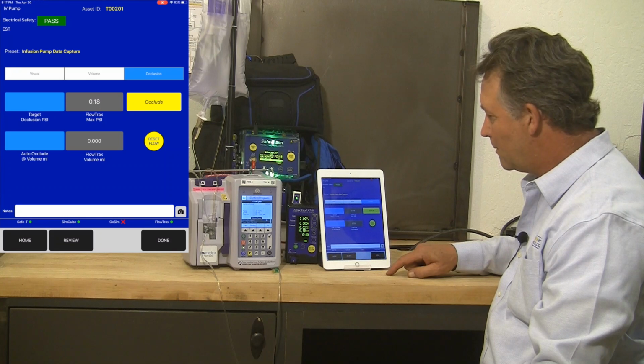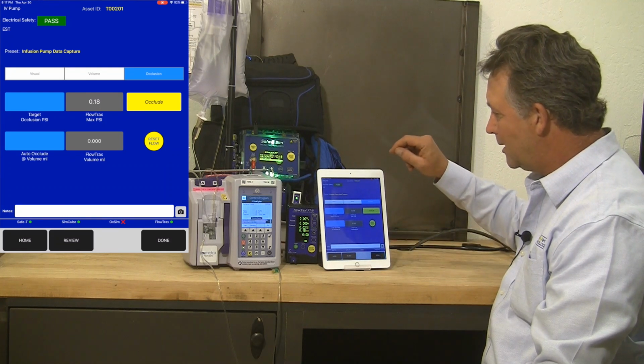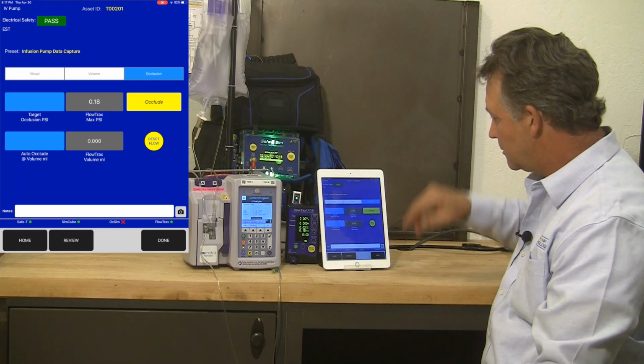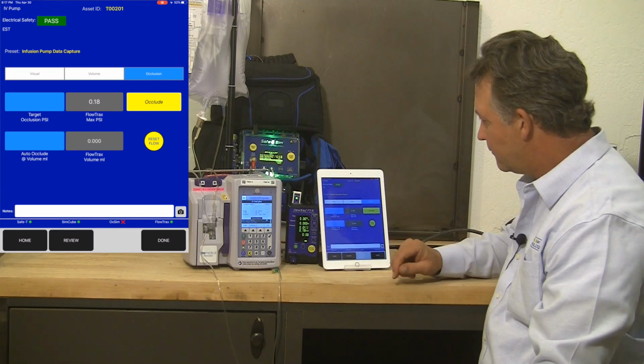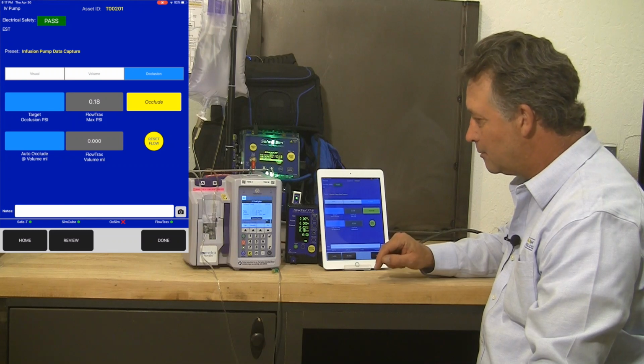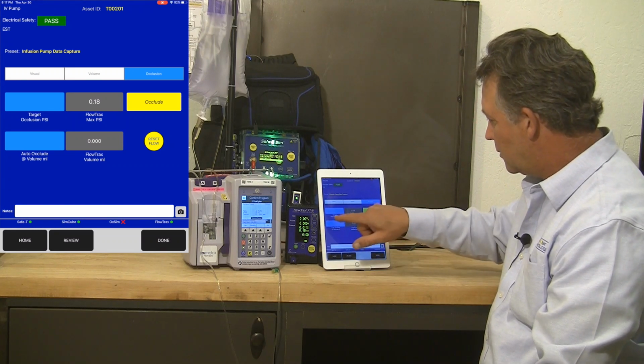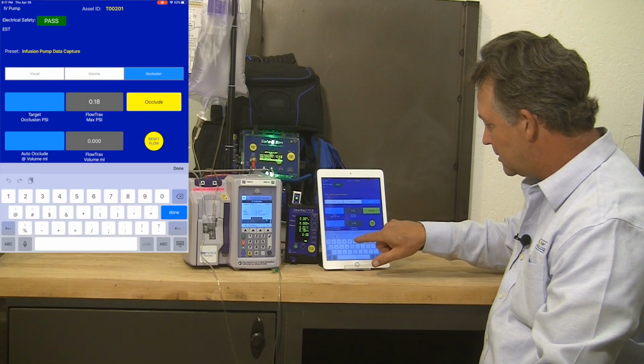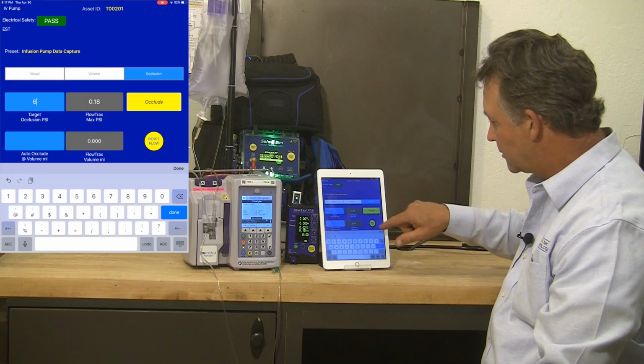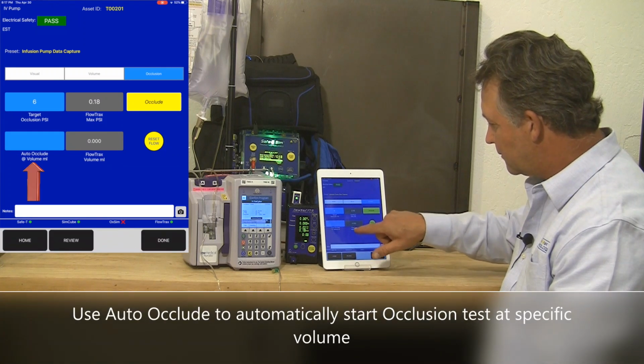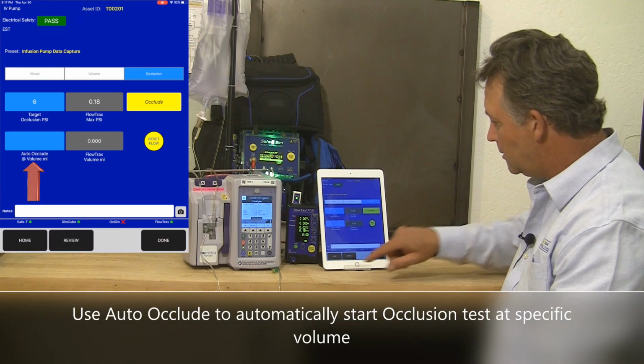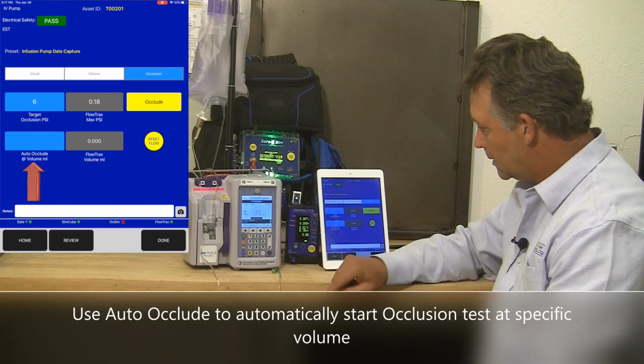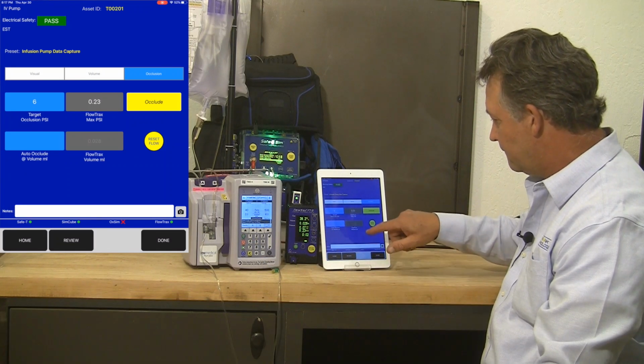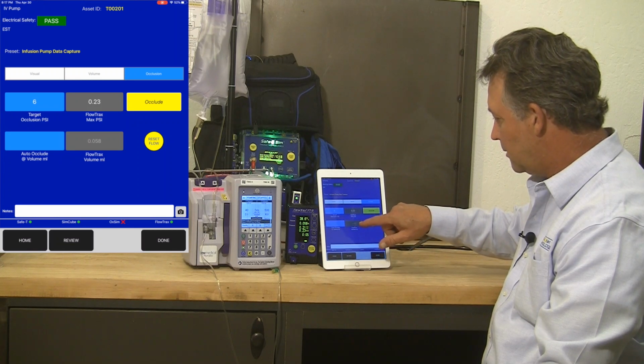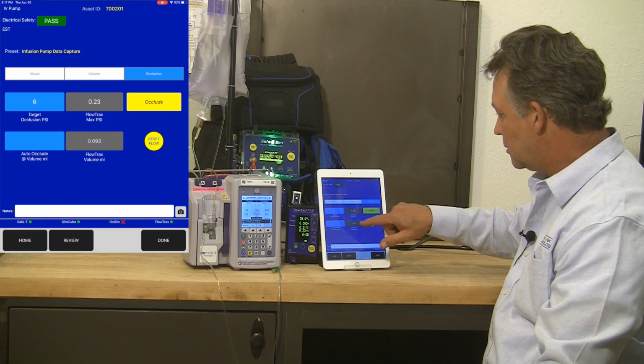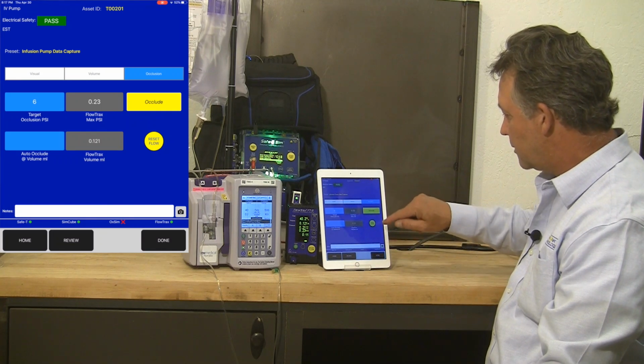Okay, so we're ready to perform an occlusion test using our app, controlling the IV pump analyzer and capturing results back. I've got the pump programmed for 40 milliliters per hour per the manufacturer requirements, and I'm going to set a target occlusion for the first test at 6 psi per the manufacturer. I don't have to reset the FlowTrax from the app because it's already at 0. I'm ready to start the pump. So the pump starts to deliver fluid, and I can see the FlowTrax volume right here on my iPhone or iPad. It's accumulating. You can see the pressure from the FlowTrax as well.